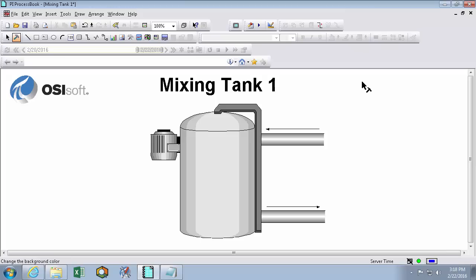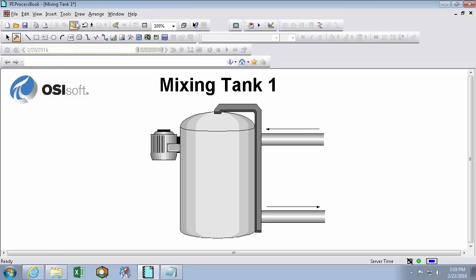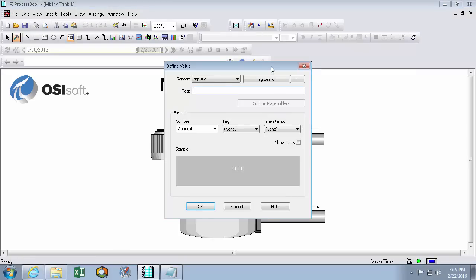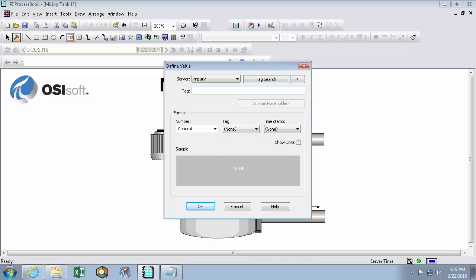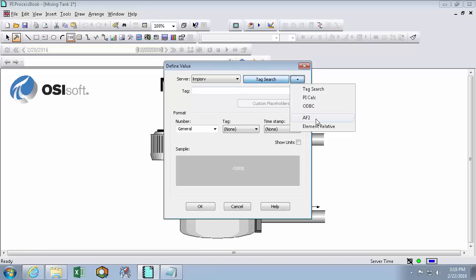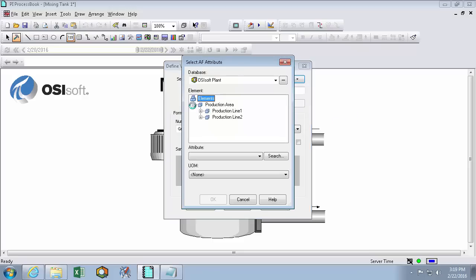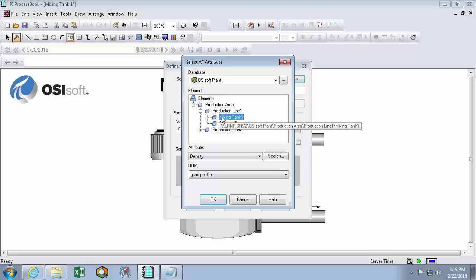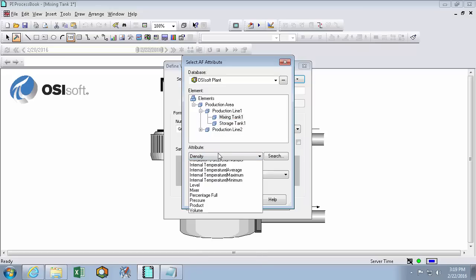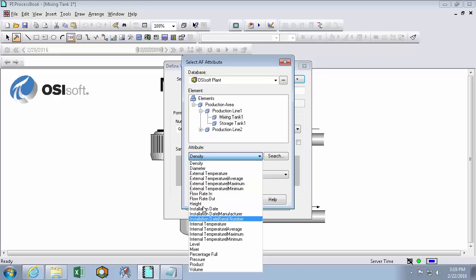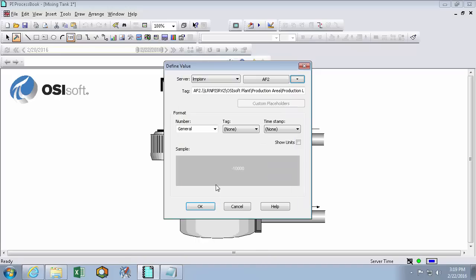So now we're ready to fill in our data. Now that we have this nice structure for how our process actually looks. So I'll start by adding some values to represent some of these flows. So what we can do is click on this value icon. I'm going to drop another box. And here I get to choose the data source that this value icon is going to represent. So if you know your PI point you can type it in there, or search for it here. But what I'll do is since I know my mixing tank 1 is built up in AF, I'm going to leverage my AF attributes and search for it here. So selecting mixing tank 1 in my tree, I know that this is a flow rate in. And we'll hit OK.